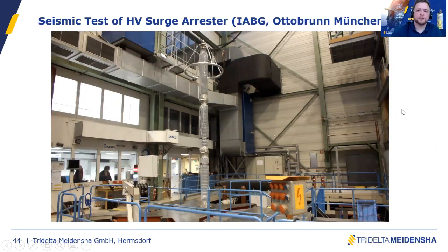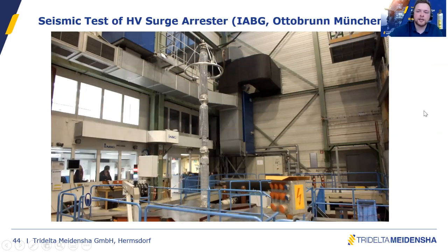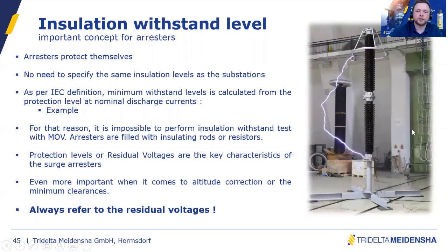So this is the test setup. We have the shaking table on the ground, we have the surge arrestor, and we will apply the bottom acceleration, and the surge arrestor will swing and will have a high amplitude on the top. And at the end of the test, it has to be structurally and electrically in a good condition, so it shall not change its properties.